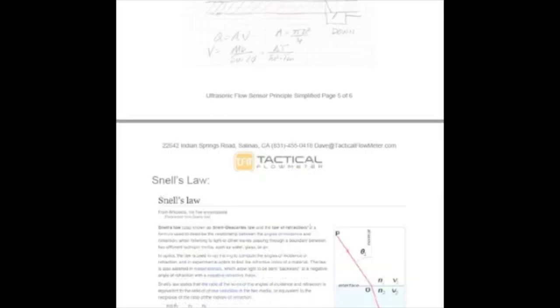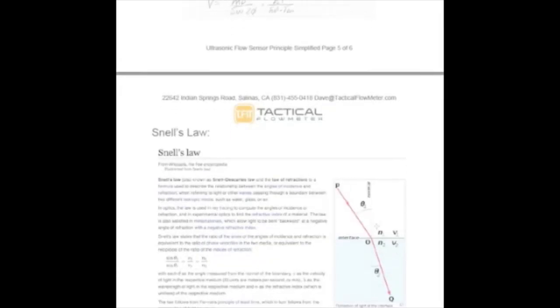So also, I just wanted to show you Snell's Law tells us how the acoustic wave travels through the material. As you send the acoustic wave, which was angled at 45 degrees from the transducer, it hits the pipe. There's some coupling material that keeps this acoustically connected to whatever it is. And then the sound travels and you can see that it bends. So this is Snell's Law. It tells you what it is.